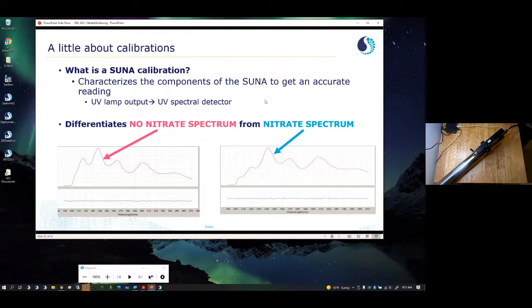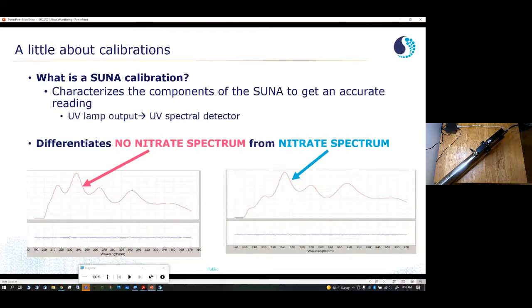Okay, so I do actually want to talk a little bit about calibration, a really important part. What is a SUNA calibration? It characterizes the components of the SUNA to get an accurate reading. You want to understand how the instrument is functioning, to be able to accurately assess the state of the water in the sensor. That goes from the lamp output to the spectral detector, and what I don't actually have on here is the electronics and the heat as well. What this does is differentiate the no nitrate spectrum that I showed before from the nitrate spectrum.